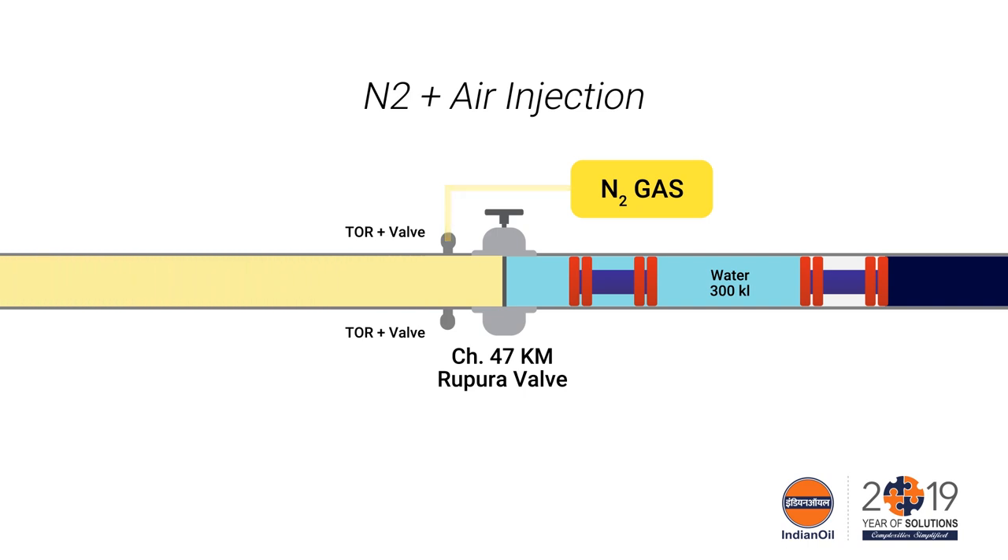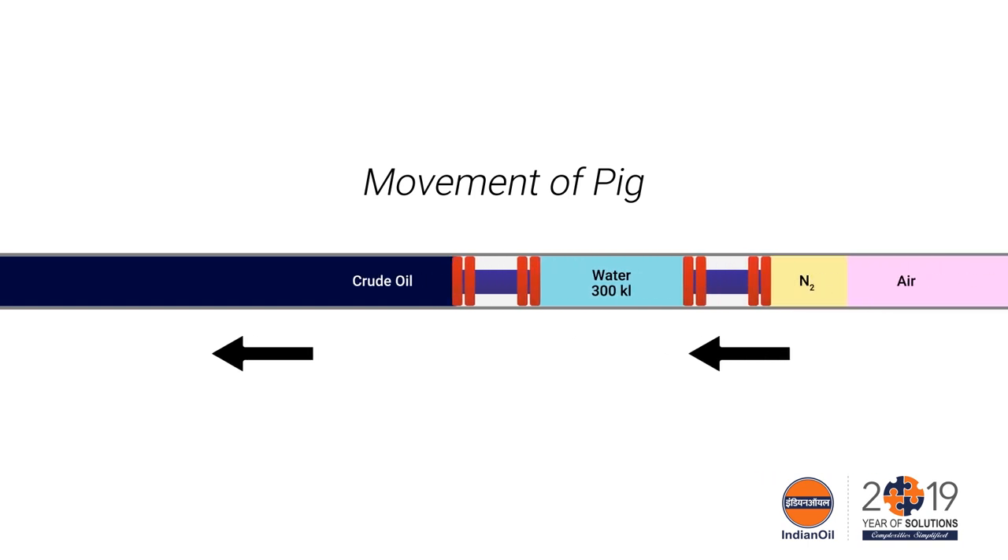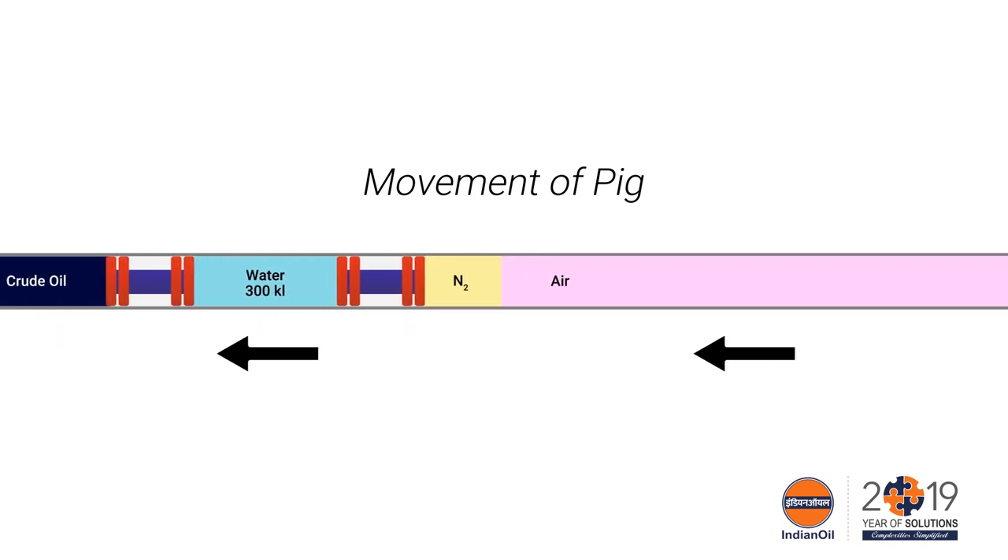After the movement of product back towards Viramgam for six kilometers, air purging was started using a compressor at Rupura through the same TORs. Here half of the pig train is moving backward towards Viramgam through the pipeline.